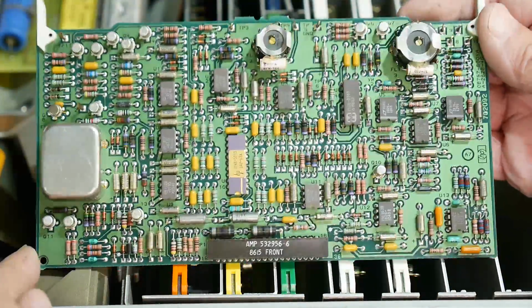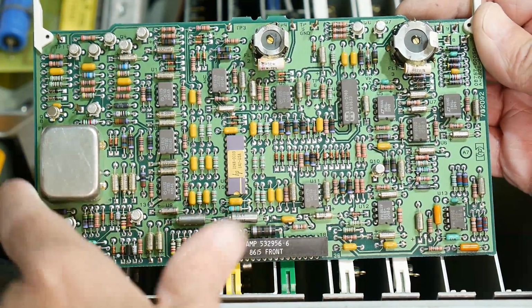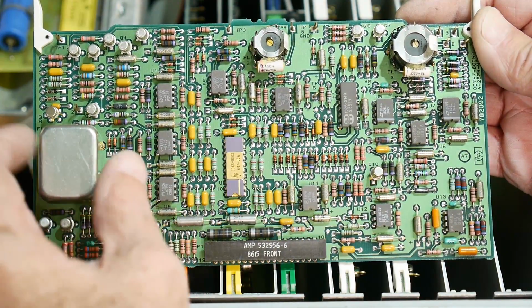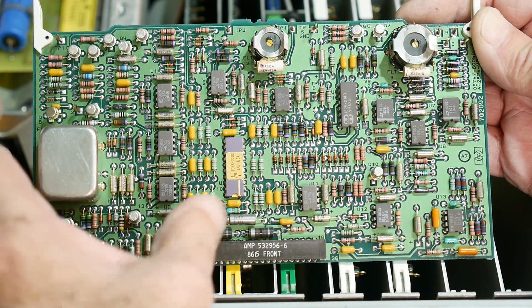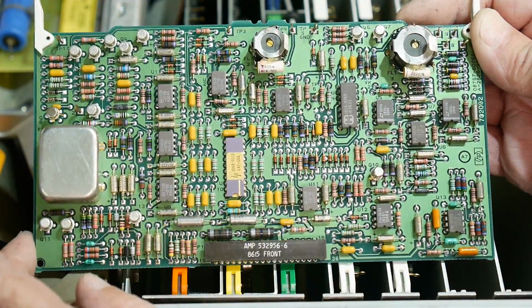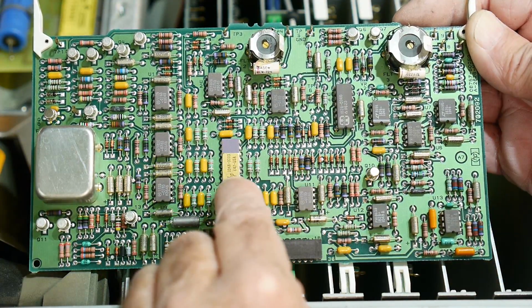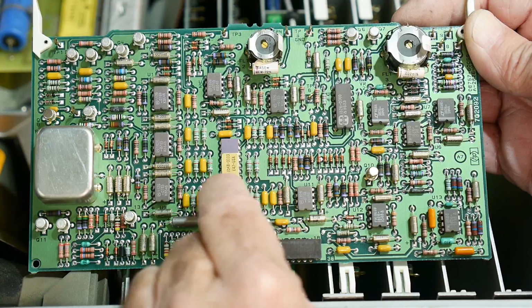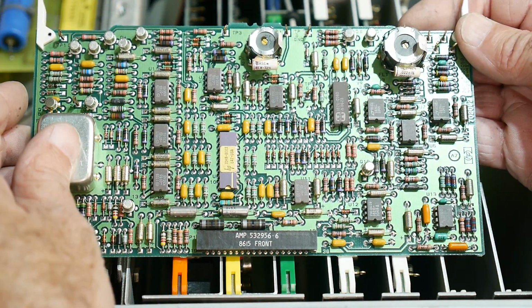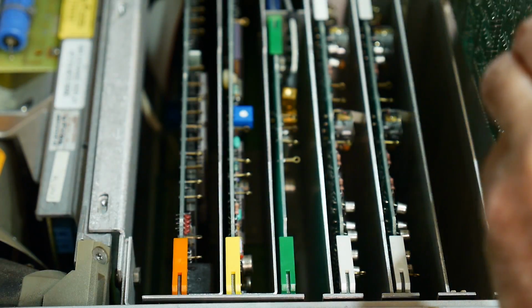So there you go. The input's going to go through a chopper stabilized front end, so that's probably in this can here. So very, very low voltages you have to deal with out of a detector. So chopper stabilized amplifier, a bunch of little parts in here, a bunch of analog parts. So you have to do a lot of filtering, and you have to do a lot of offset correction and stuff like that. And it looks like there's a custom chip here, an HP custom chip. So you couldn't repair this. You'd have to get an HP part. Anyway, so there's three of those that are identical.